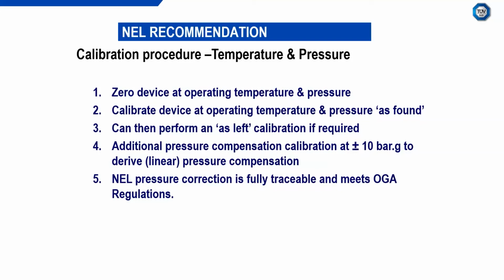The pressure effect is basically the slope, the gradient, and adjusting the as found to the as left you can think of as being like the intercept, the c, in y equals mx plus c. So you can then do the additional pressure compensation calibration at plus or minus 10 bar, for example, to derive this correction. And then you have this pressure correction that's fully traceable and meets regulations. So that's what we recommend, and that's pretty much what we do day in, day out with our elevated pressure and temperature flow facility as a commercial organisation.